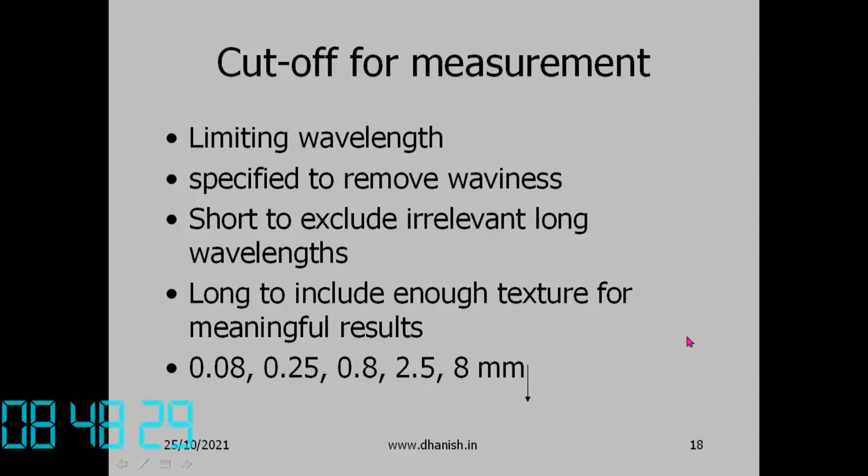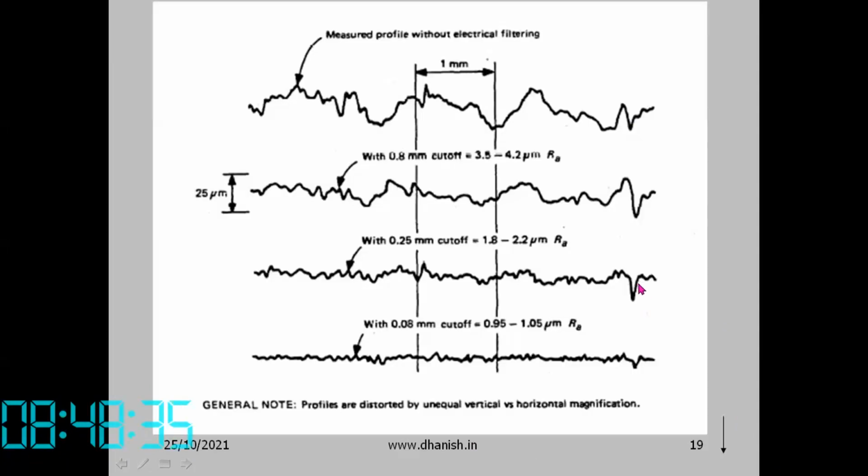Okay, so that is the specification for cutoff. So what happens when you change the cutoff? Take the same surface, the measured profile without electrical filter. In the olden days, it was not digital filtering. When we started developing surface measuring instruments, microprocessors and all were not there.